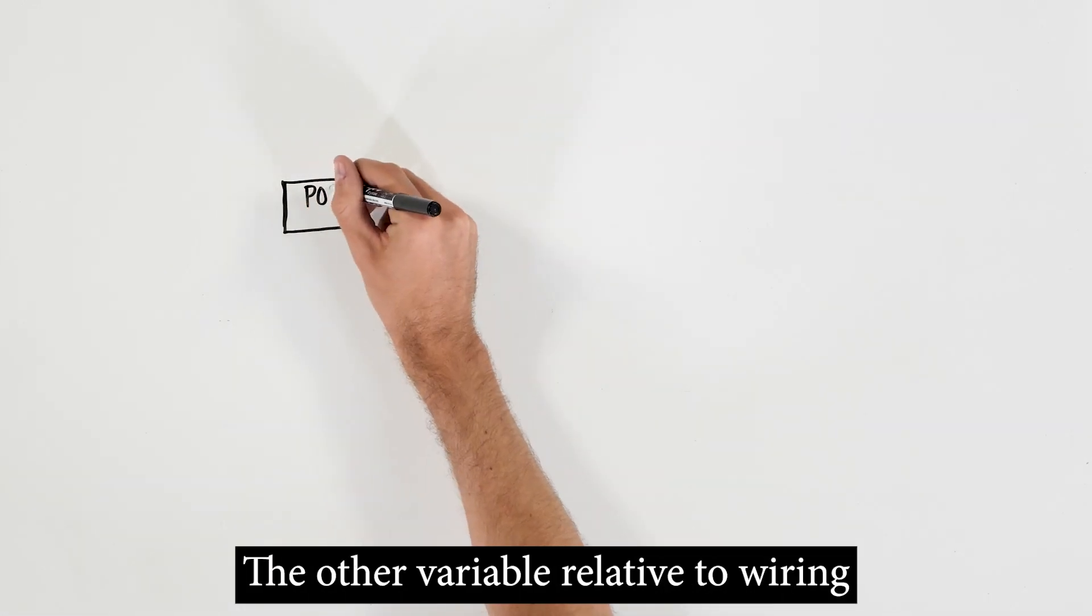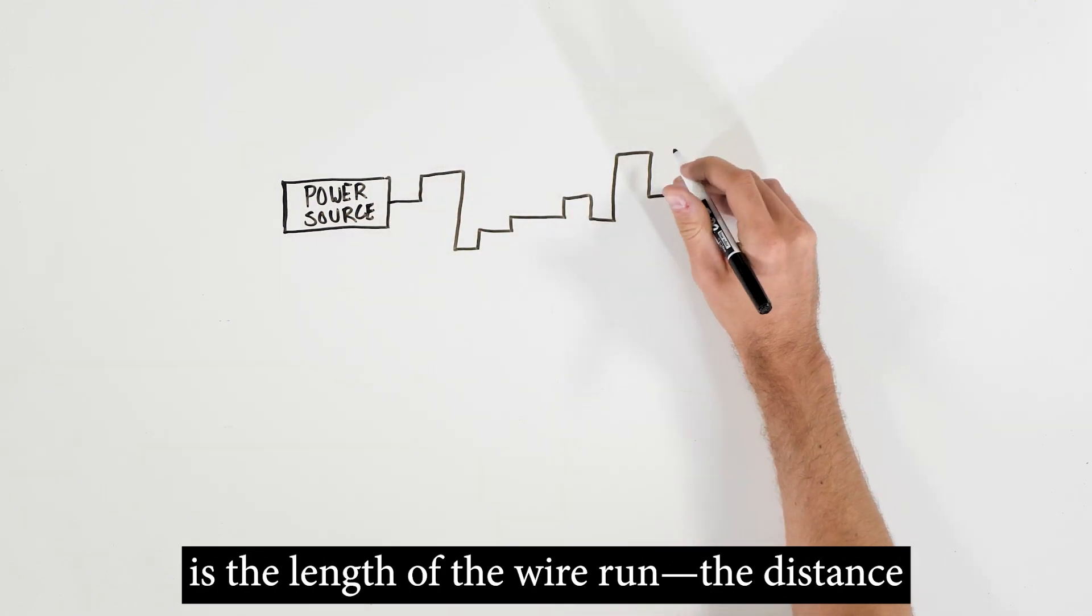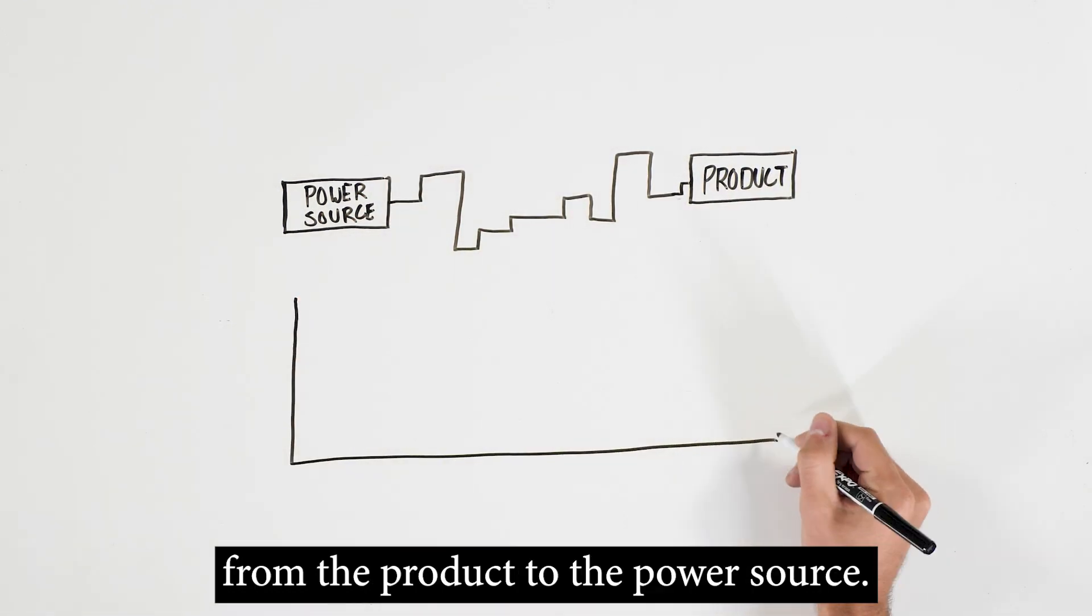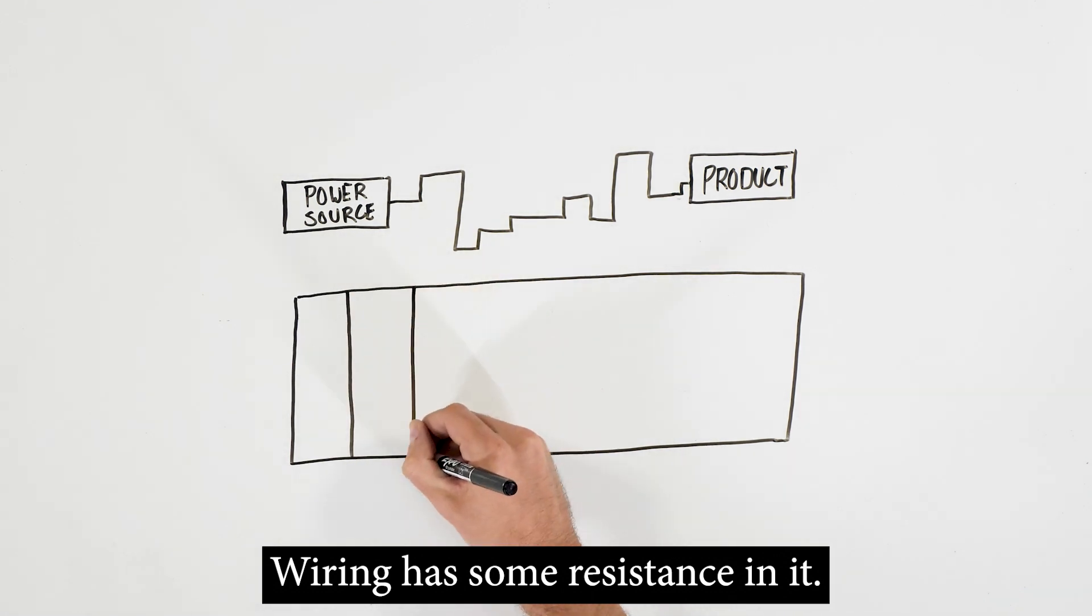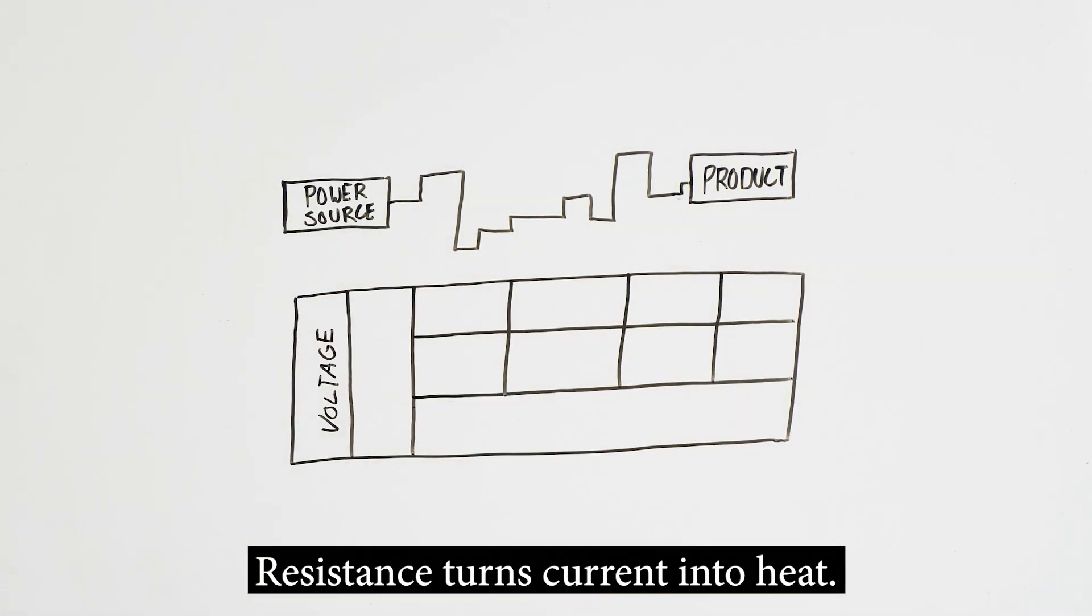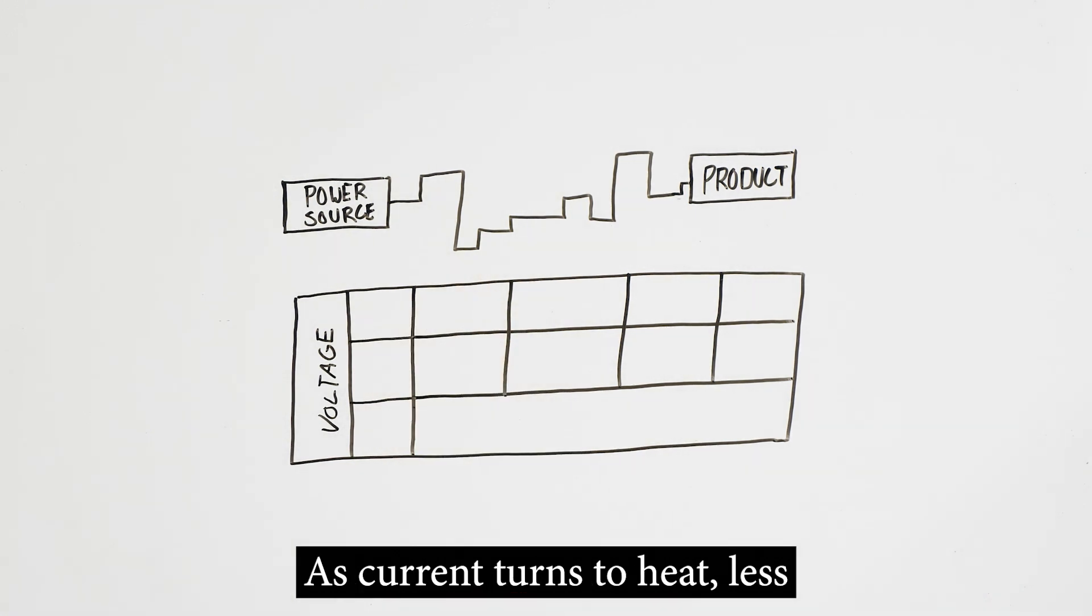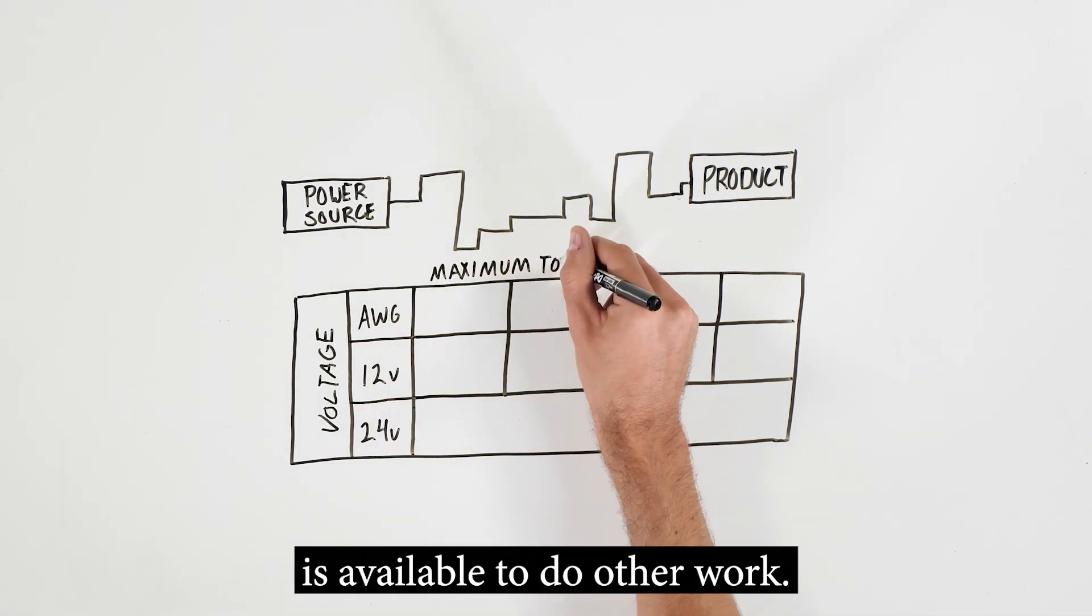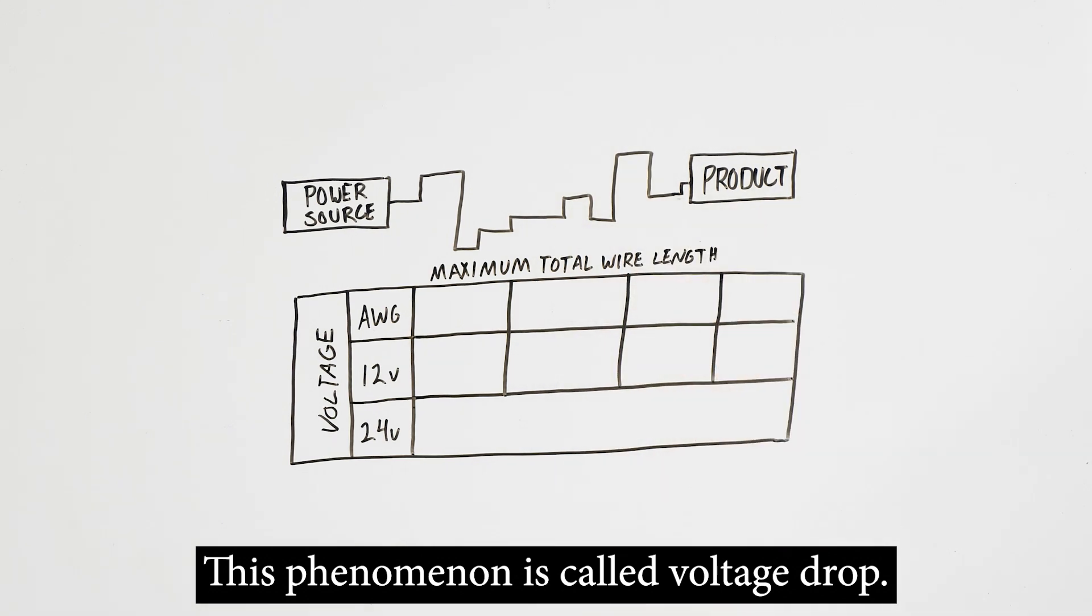The other variable relative to wiring is the length of the wire run, the distance from the product to the power source. Wiring has some resistance in it. The longer the wire run, the more resistance there will be. Resistance turns current into heat. As current turns to heat, less is available to do other work. This phenomenon is called voltage drop.